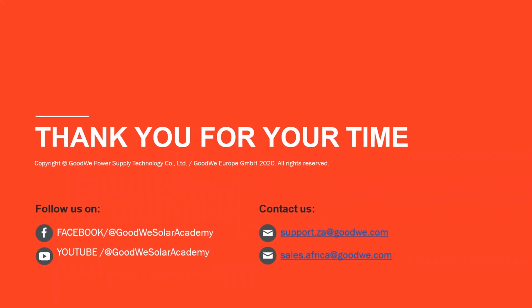So our R&D is working on that. We should have a firmware release. I'm just waiting for confirmation within this week or next week. Well, this week's already over, but we do have a newer firmware, and I am just confirming and testing that this is working correctly. But we do hope to have this out quite soon. This will then allow us to adjust a negative export value. So instead of going to 0, you can put -50, -100, just to make sure that there is always a positive flow from the grid to ensure that those meters do not trip off.